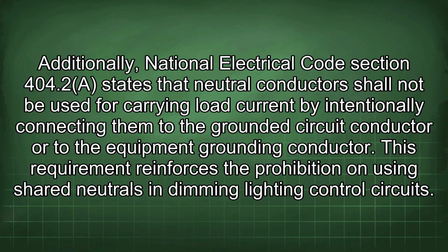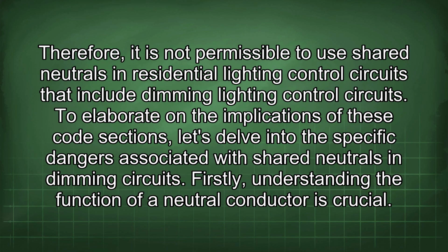Additionally, National Electrical Code Section 404.2 states that neutral conductors shall not be used for carrying load current by intentionally connecting them to the grounded circuit conductor or to the equipment grounding conductor. This requirement reinforces the prohibition on using shared neutrals in dimming lighting control circuits. Therefore, it is not permissible to use shared neutrals in residential lighting control circuits that include dimming lighting control circuits.